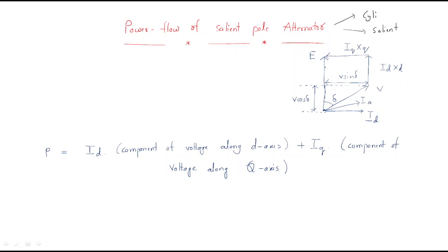Just look at the salient pole alternator phasor diagram. V is the output voltage, V is the load voltage. For some phase angle phi, armature current will be developed. This is the load current. Armature current will be divided into two parts: one is the direct axis current and another one is the quadrature axis current. This is the quadrature axis current iq. E means open circuit voltage — the voltage developed across the armature open circuit terminals without load.